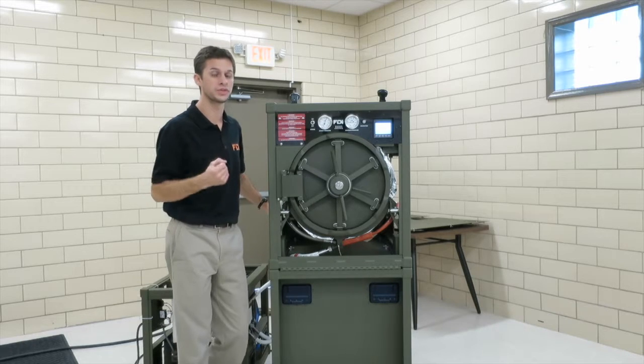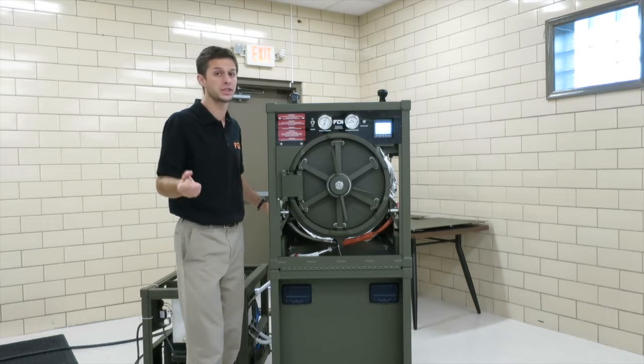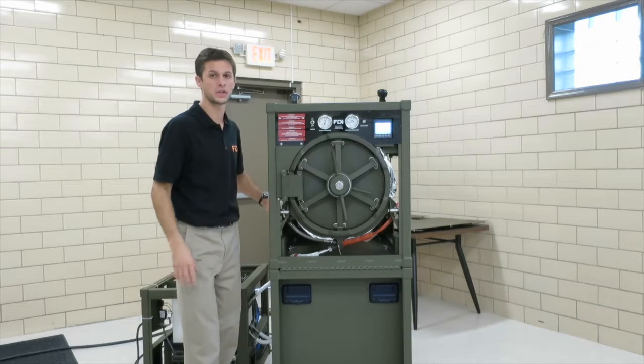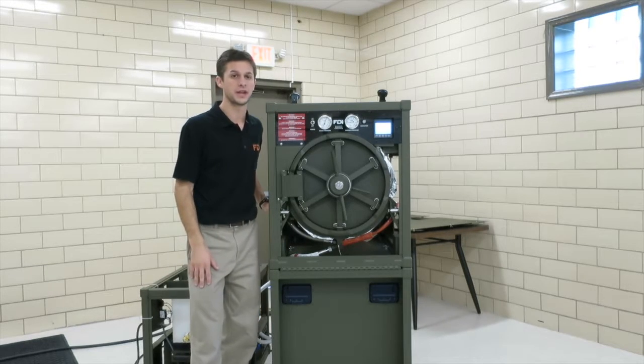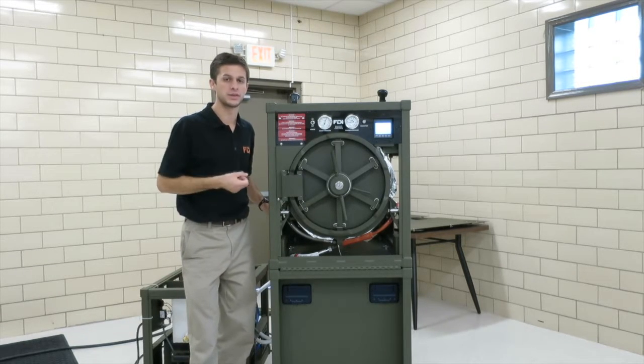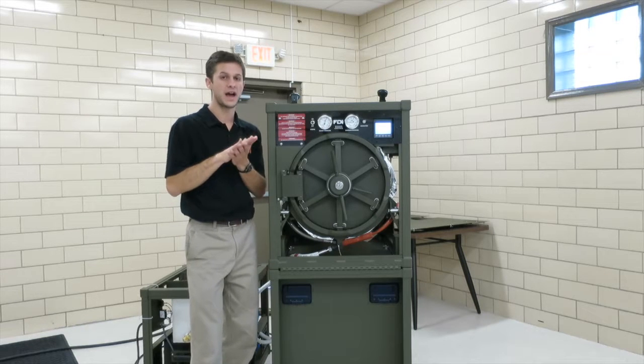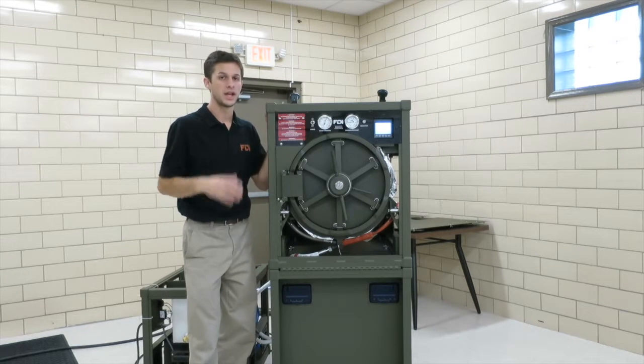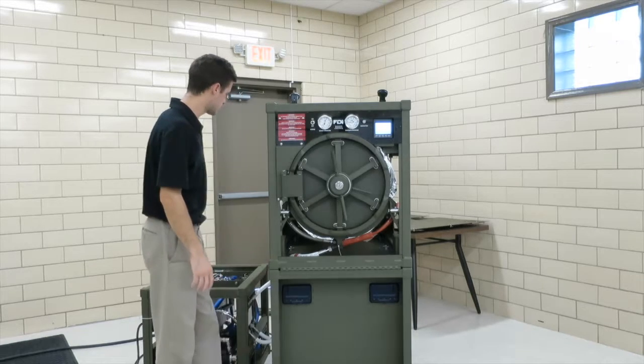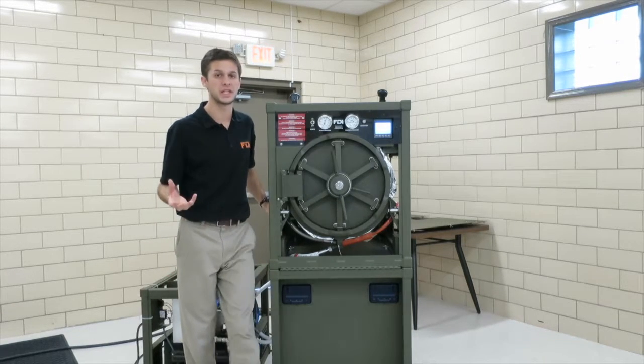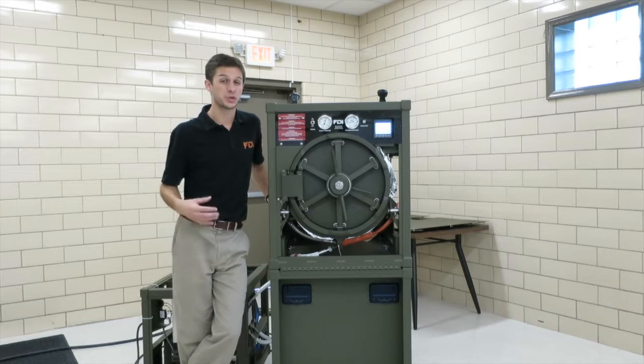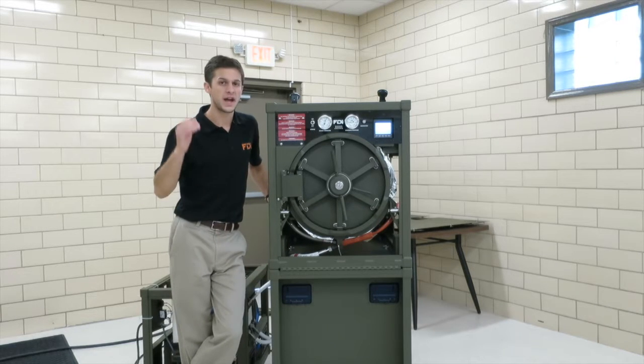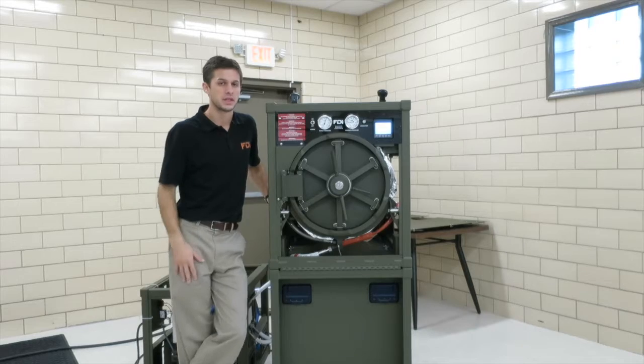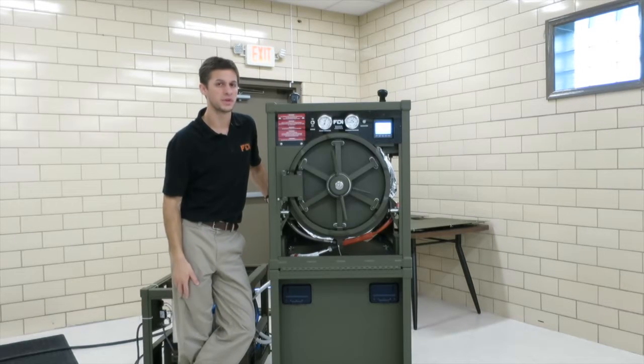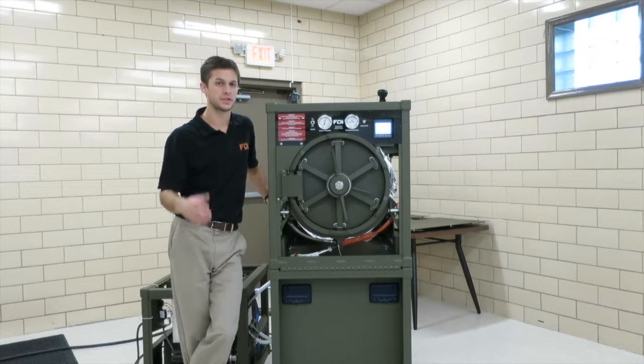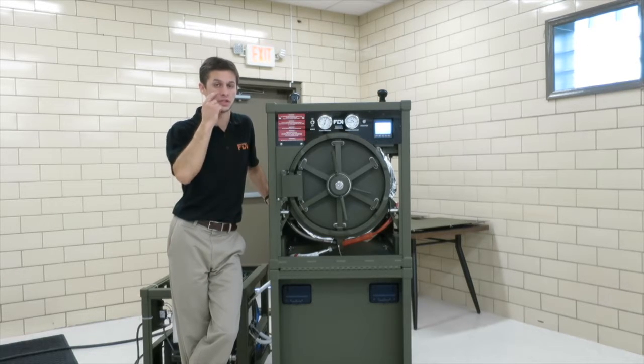The adapter that pulls the vacuum could be clogged. Maybe your vacuum hose is clogged. There's a lot of things you can check in your manual. But what's going on there is somehow the vacuum is not being pulled in the correct amount of time. The water recovery system, the water can also heat up. As that water heats up and gets really hot, vacuum performance does decline a little bit. Shouldn't be to the point where you throw this alarm, but if you're running a really hot environment, you may have insufficient vacuum 06 alarm.